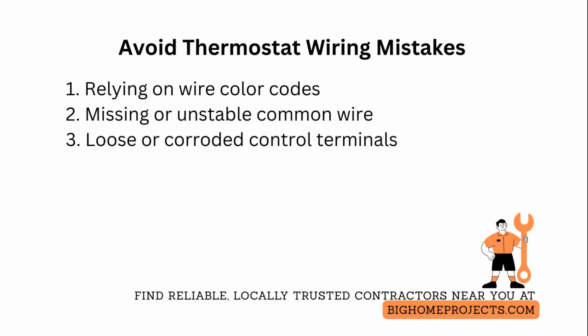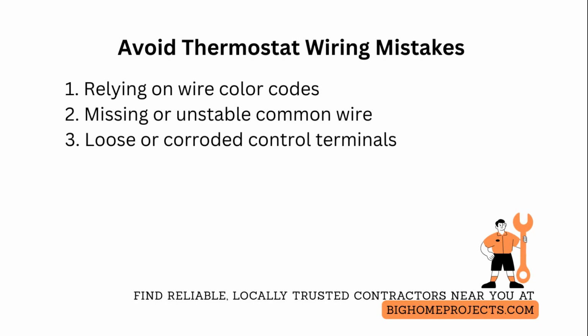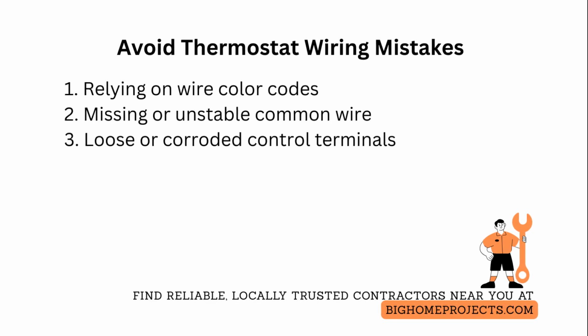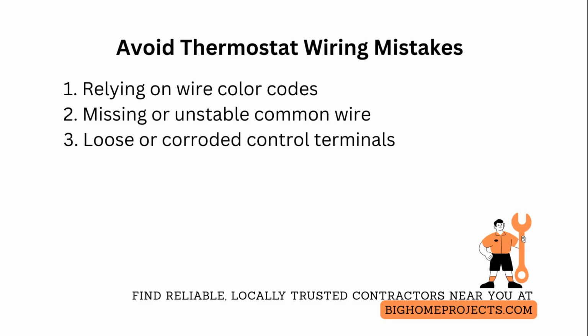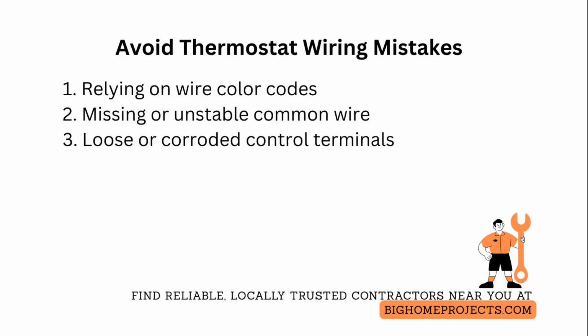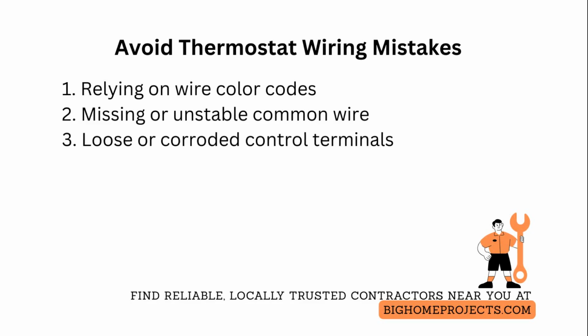One of the typical errors is assuming thermostat symptoms are device faults, when the real problem is loose or corroded control board terminals or failing relays. Correct this by inspecting and tightening terminals, replacing damaged connectors, and confirming relay operation during thermostat calls to isolate whether the thermostat or the control board is at fault.